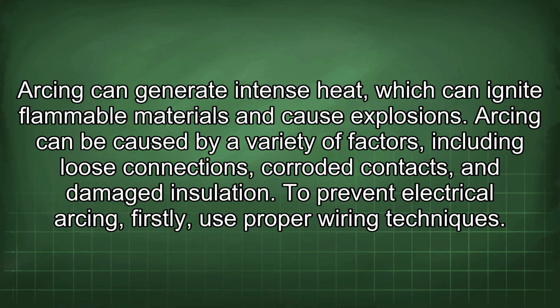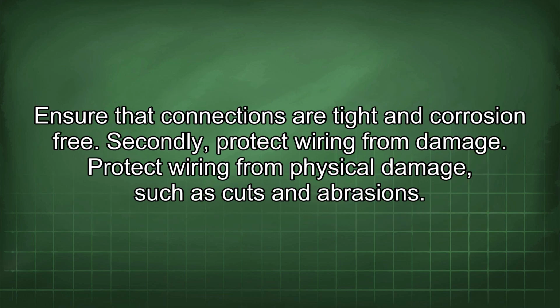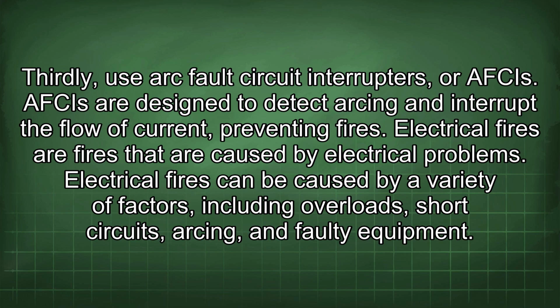To prevent electrical arcing, firstly, use proper wiring techniques. Ensure that connections are tight and corrosion-free. Secondly, protect wiring from damage. Protect wiring from physical damage, such as cuts and abrasions. Thirdly, use arc fault circuit interrupters, or AFCIs. AFCIs are designed to detect arcing and interrupt the flow of current, preventing fires.